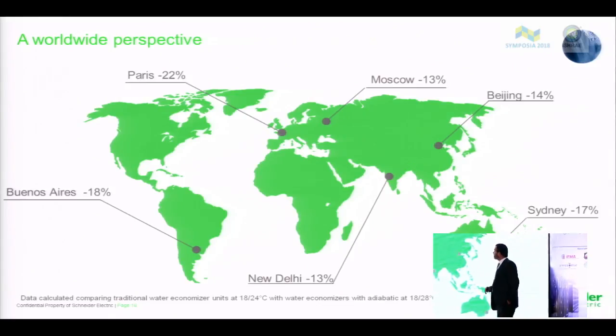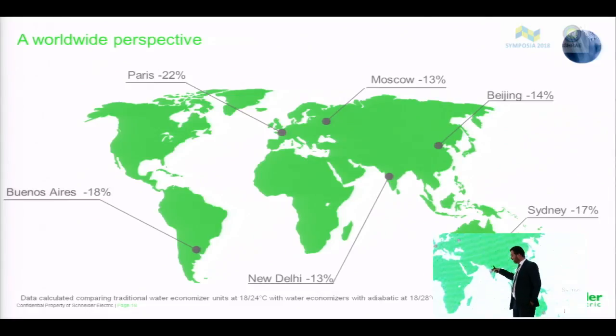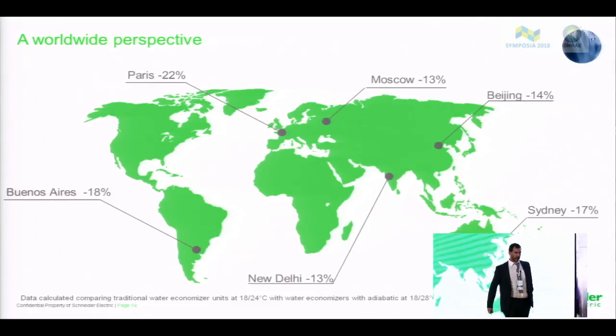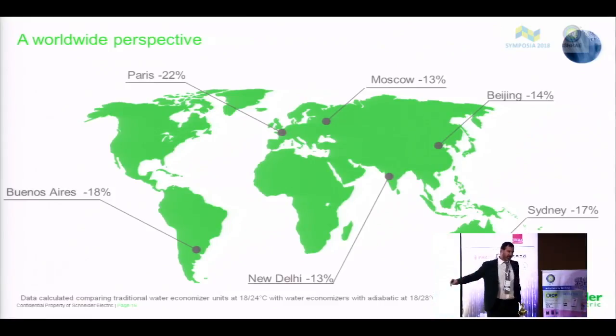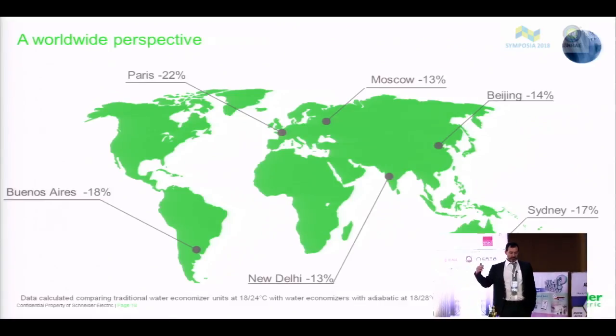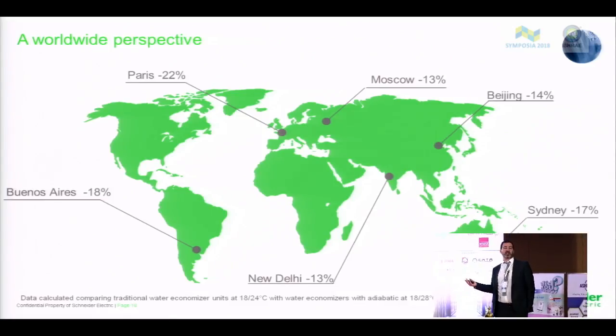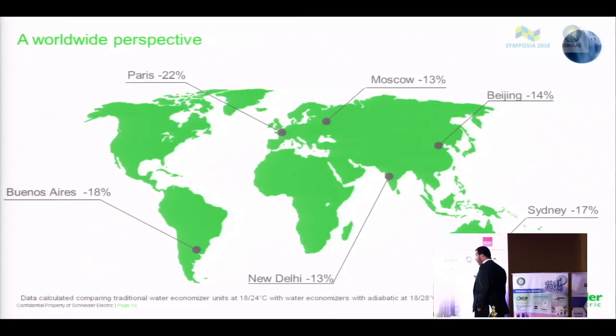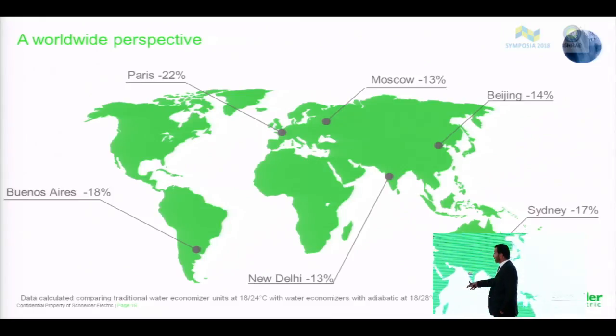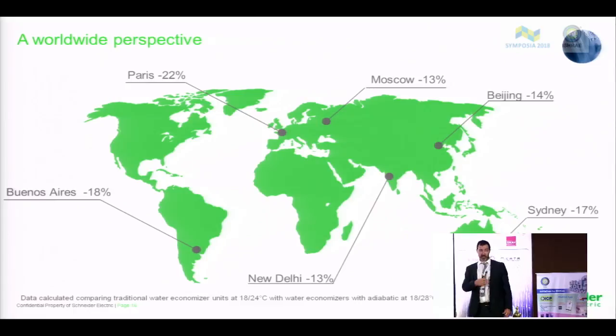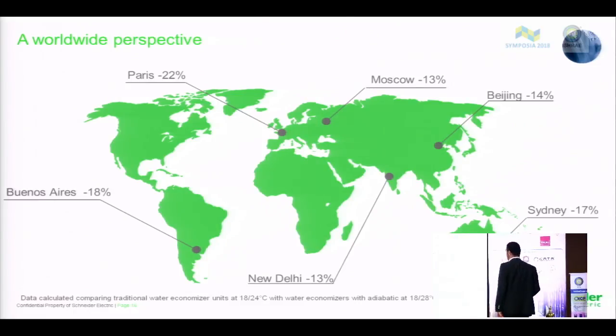It's interesting to see that the result in Delhi are similar to the benefit we have in Moscow, although the climatic profiles are different. This is because Moscow is pretty cold, and the free cooling, it's a traditionally fantastic place for free cooling. But definitely, with this system, we can have the same result or similar result that we currently have in Moscow, even in Delhi. So that's definitely a change of the traditional approach we have on the free cooling on the adiabatic. So as a suggestion, it would be a good point to analyze if the adiabatic could be or not a part of the equation when we design and we select the chiller. Or an air economizer as well.